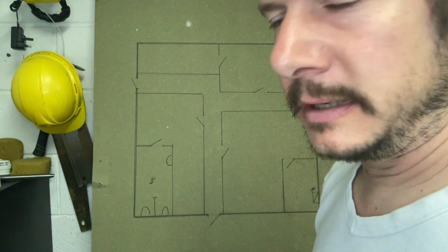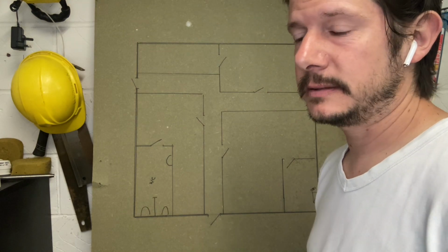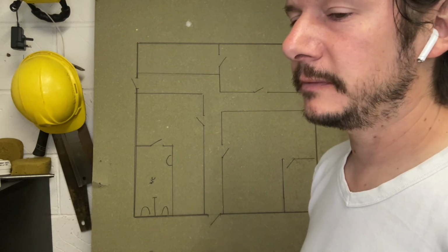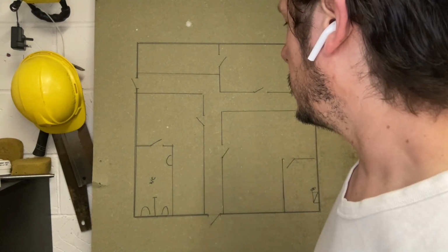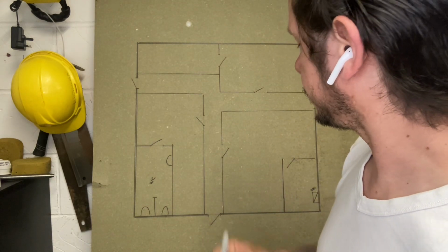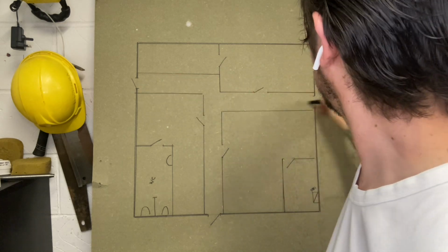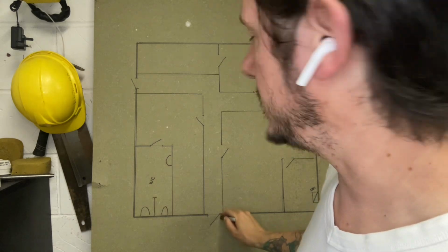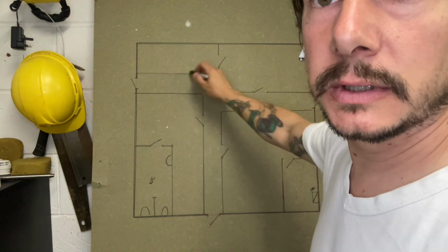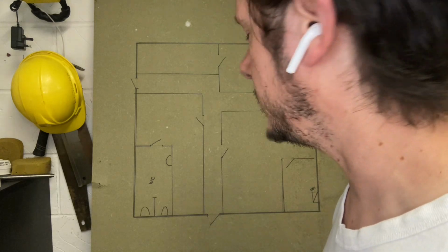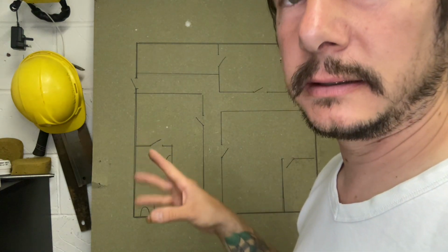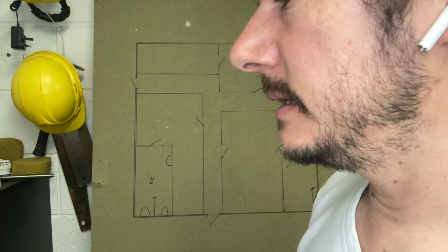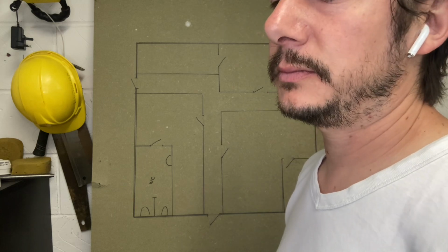So in reverse order, L5, your fire engineer has said, I'm balancing everything out with other things. We've got a very good management system in place. So all I want is detectors in the escape routes, call points, places that lead to places of eventual safety. No sounders, because I'm going to make the lights flash. I'm not going to start drawing in L5 stuff because it's lots of fancy stuff going on. And again, if you're getting into the realms of pricing for L5 work, then probably beyond the help of these videos anyway.